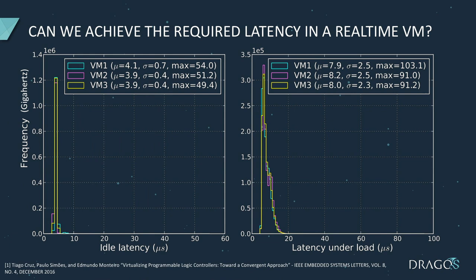Those are pretty short windows you need to adhere to in order to prevent a process from tripping on the backplane virtualization. But there was a study done by IEEE back in 2016 where they tried to address this issue using commodity Intel-based hardware to create a PLC virtualization environment. They were able to successfully drop the latency well below the requirements — to 10 or 20 microseconds — by disabling hyper-threading and some built-in virtualization technologies more focused on throughput than latency. So we do know it is possible to virtualize the backplane of these PLCs.